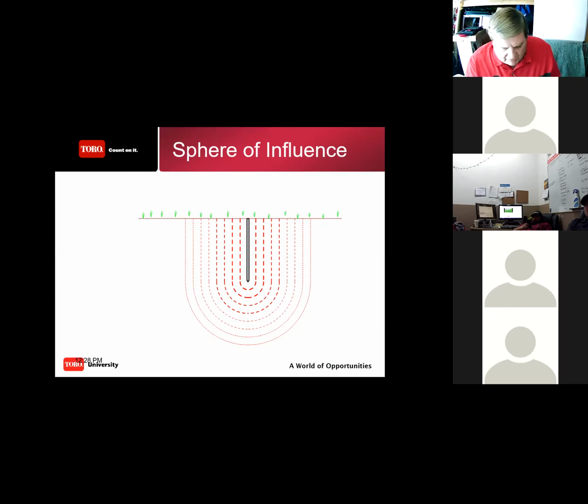Moving on. So it's the sphere of influence. If you get a surge, a lightning surge, a power surge of some sort, it's getting swallowed up by the 2-wire path. It's making its way towards the controller. It's making its way towards the decoder. When it comes to the decoder, it's supposed to channel through the surge device out to the ground rod and dissipate into the soil, making this sphere of influence pretty large. Typically, the length of the rod is your sphere of influence. So if it's an 8-foot rod, you've got 8 feet from this end to the rod and 8 feet from the outer edge into the rod, which is my sphere of influence. I don't want anything in that area. I want to be able to dissipate the surge away from any wire path.